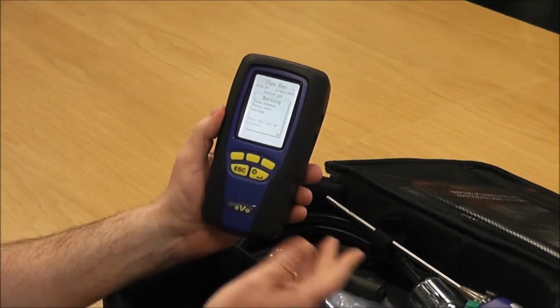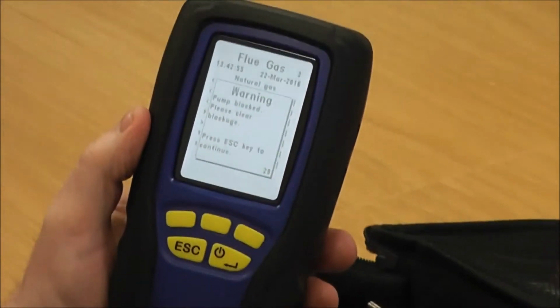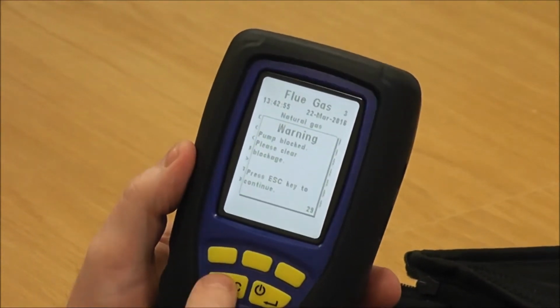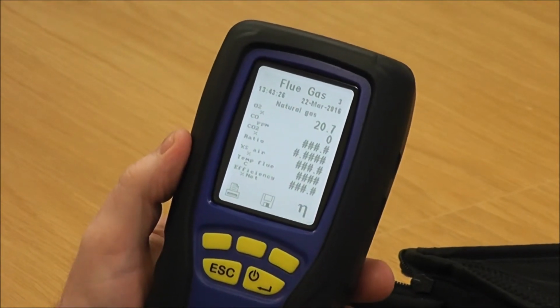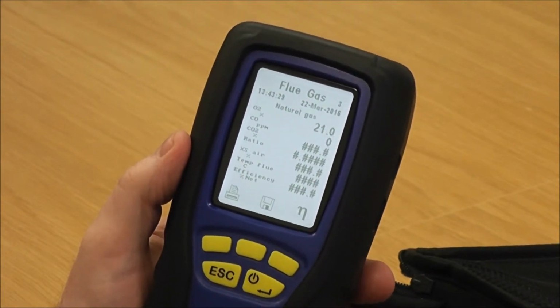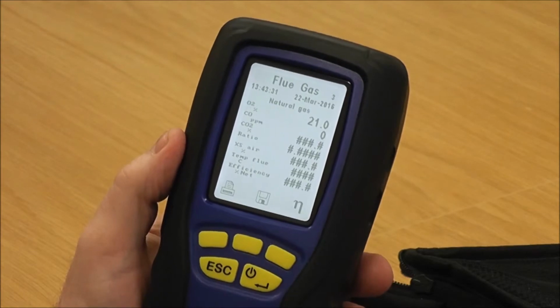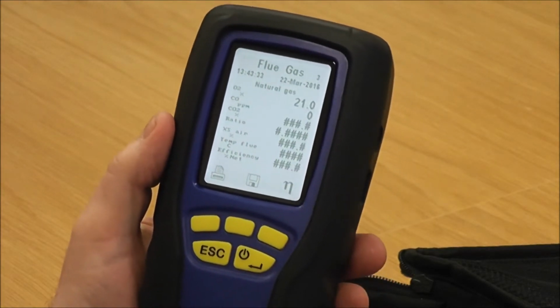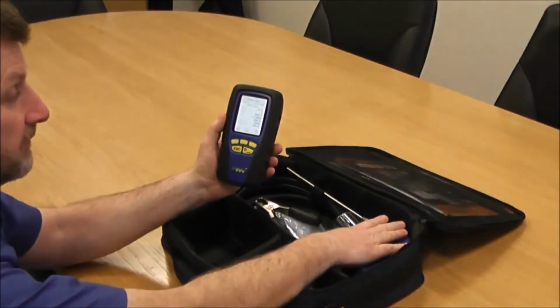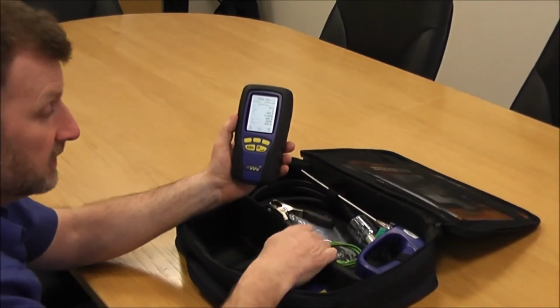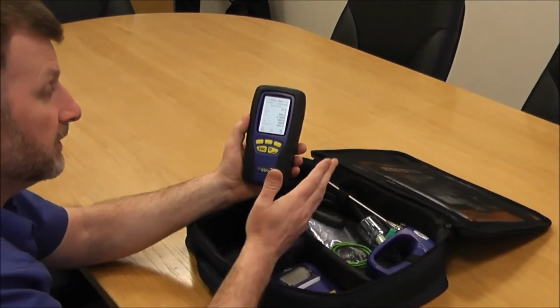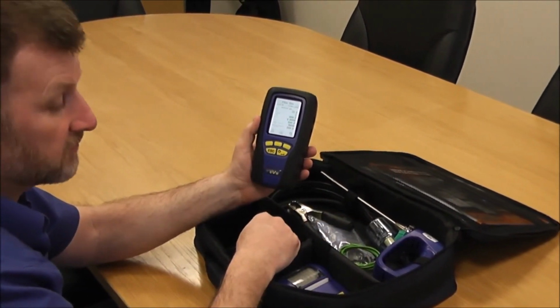And because we've come up pump blocked, if I press escape now and the pump comes straight back on, which it does, then we know that there's no problem with the pump and there's no problem with the internal tubes. So combined with the flue probe checks, that shows us that the overall integrity of both the flue probe and the instrument itself all looks fine and good to go.